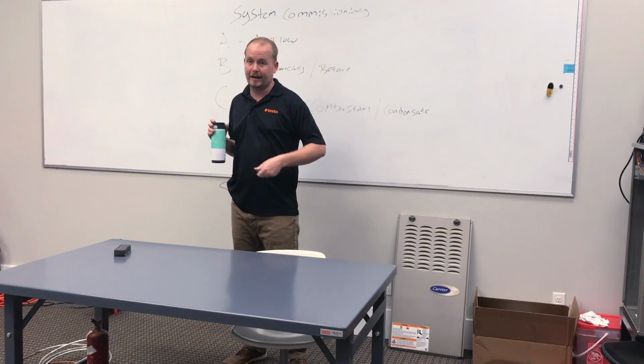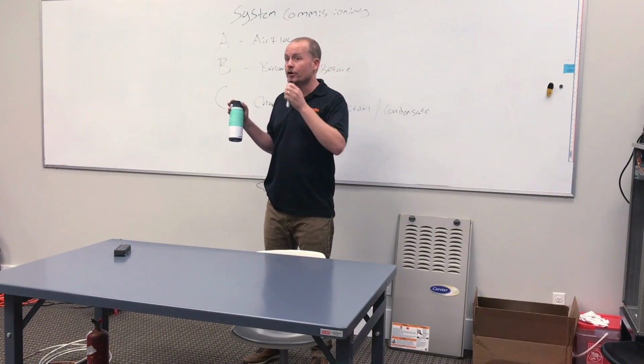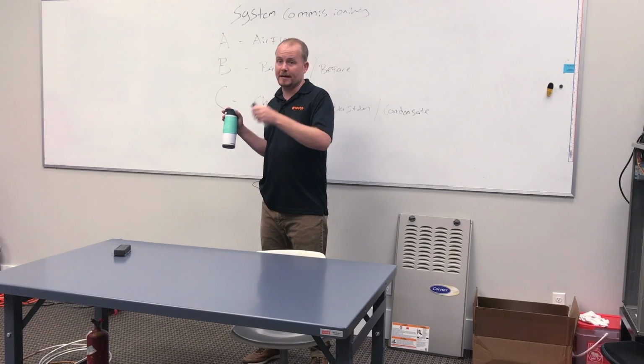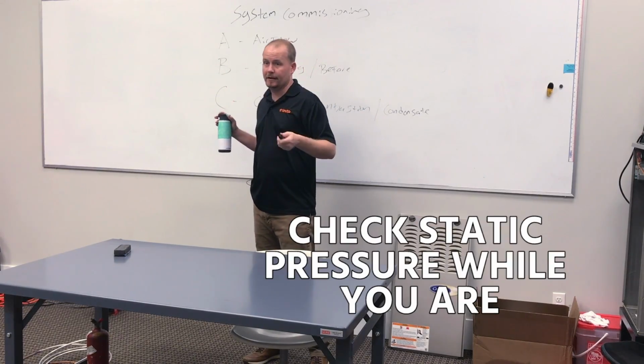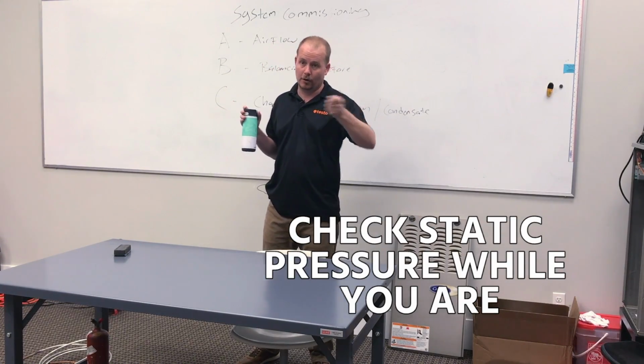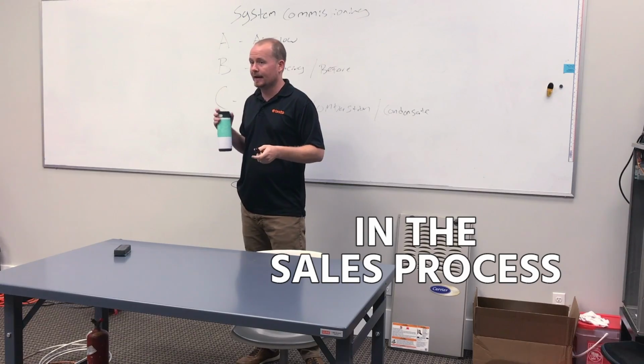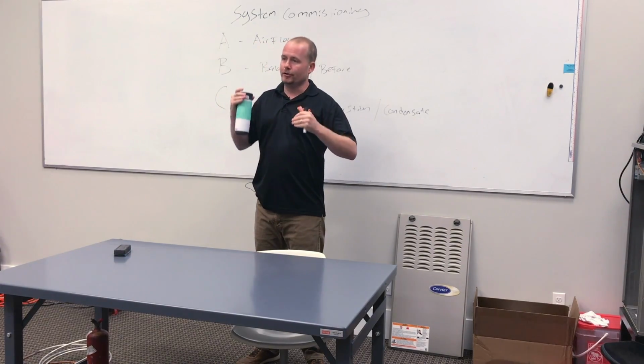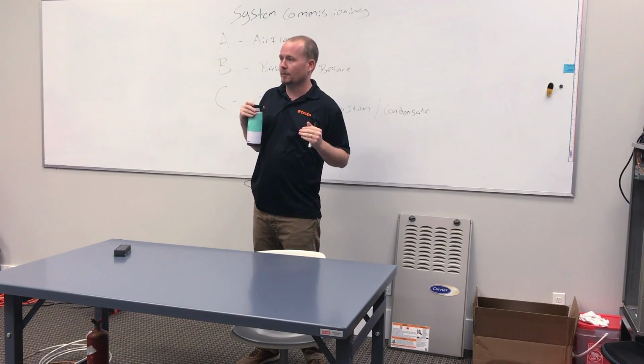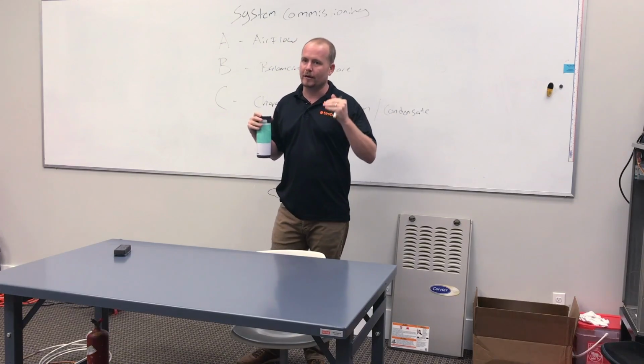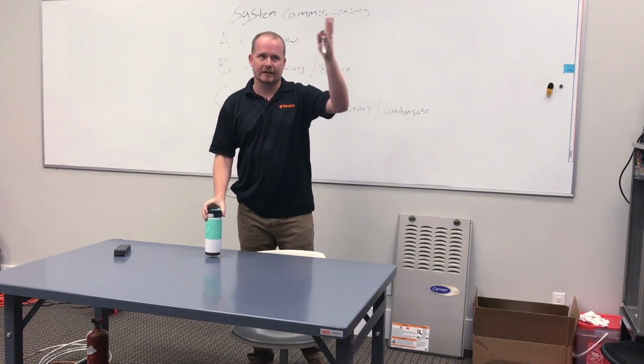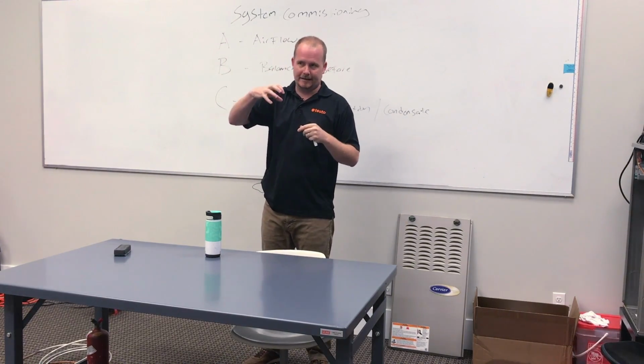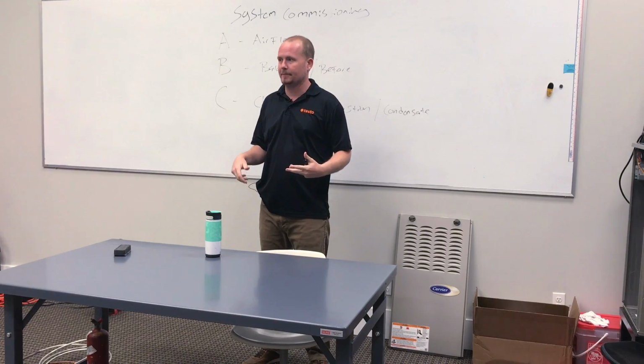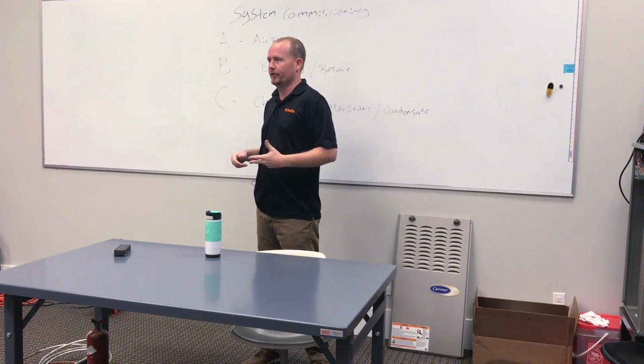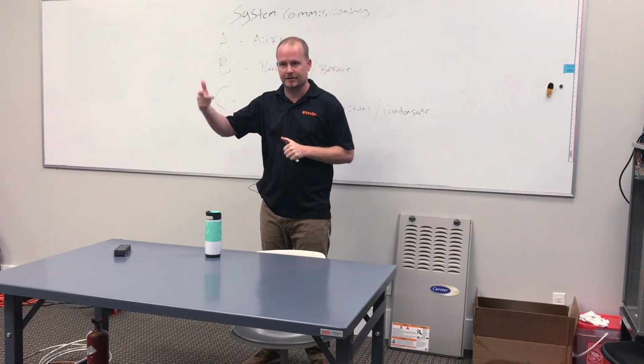When it's 0.7, 0.75, 0.8, it's no problem. And you can know whether or not it's going to be a problem beforehand. The easiest way is to check static pressure while you're there in the sales process. And then if you want to get real fancy, you can use the fan charts and compare it to what the new system will be and all that. But you get good enough that you're able to look at the ductwork, look at what's connected to it, look at the existing system static pressure, and tell whether or not it's going to be a problem. But it takes paying attention, right?